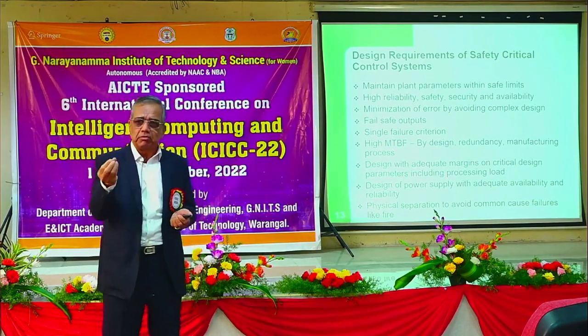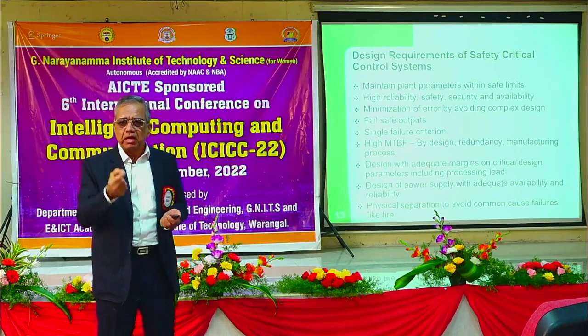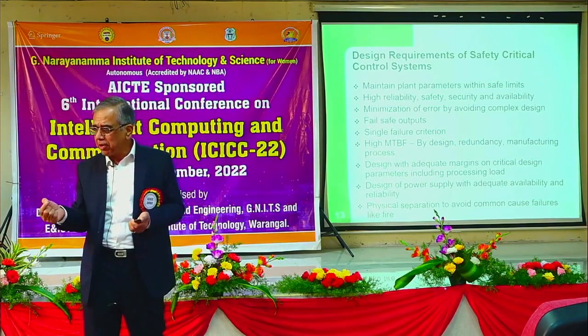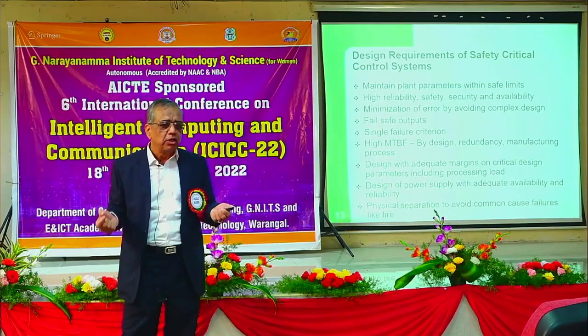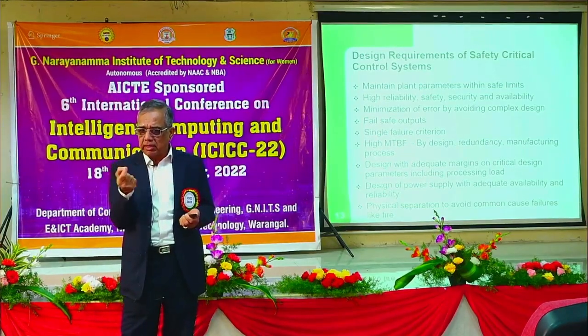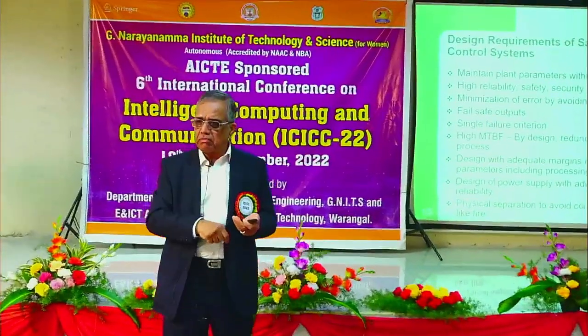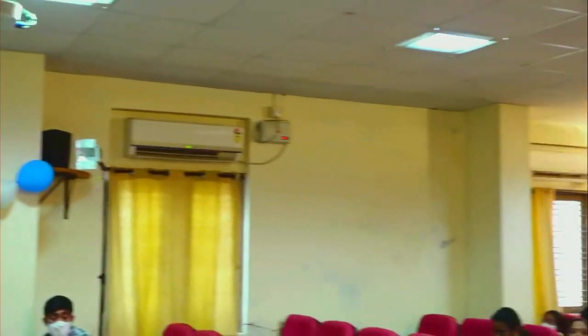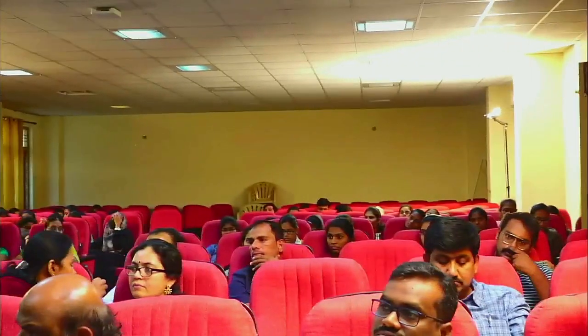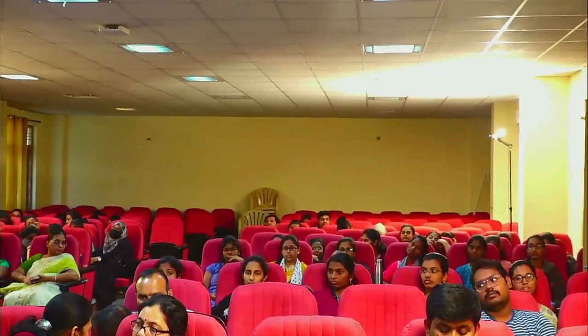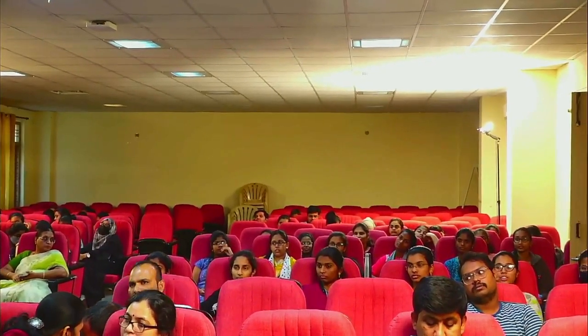Suppose you are measuring a flow, one sensor is giving 10, another is giving 10.1, another is giving 10.3, you select the median, the central value. That value is used for calculation, and when output is generated, again there is a median selection. Similarly, for digital input, we do 2 out of 3. 3 inputs are taken, you take any 2 which are either both true, both false, or whatever. So, 2 out of 3 we take. So, this is what we do in single failure criteria.